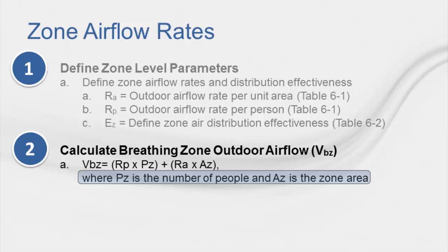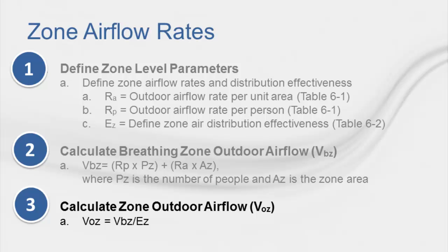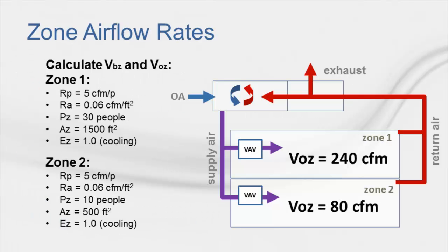In equation 6-1, P sub Z represents the number of people in the zone, and A sub Z represents the zone's unit area. In Step 3, you can calculate the zone outdoor air flow, V sub OZ. This is the outdoor air flow rate that must be provided to the ventilation zone by the supply air distribution system. The zone outdoor air flow rate is calculated using the equation V sub OZ equals V sub BZ divided by E sub Z. So now that we know the equations for the zone level outdoor air flow rate calculation, we can calculate V sub BZ and V sub OZ for zone 1 and zone 2.